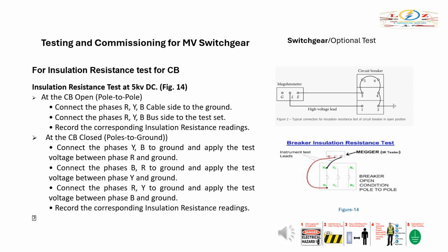With the CB closed, connect the phases Y, B to ground and apply the test voltage between phase R and ground. Connect the phases B, R to ground and apply the test voltage between phase Y and ground. Connect the phases R, Y to ground and apply the test voltage between phase B and ground. Apply voltage in accordance with the manufacturer's published data. In the absence of manufacturer's published data, use Table 100.1. Record the corresponding insulation resistance readings.